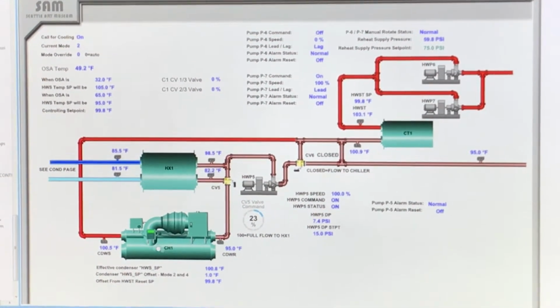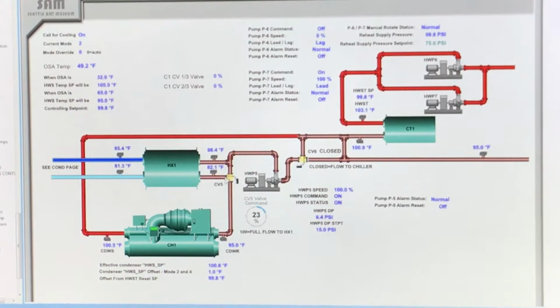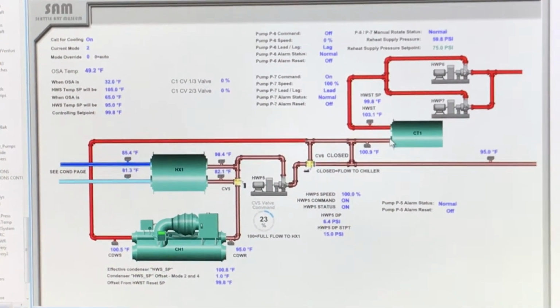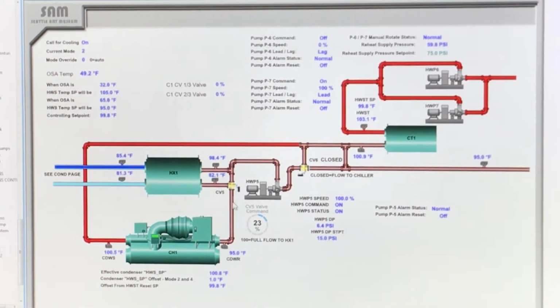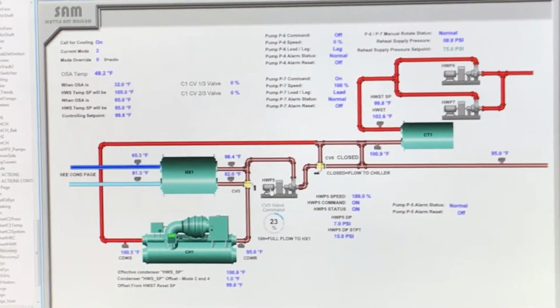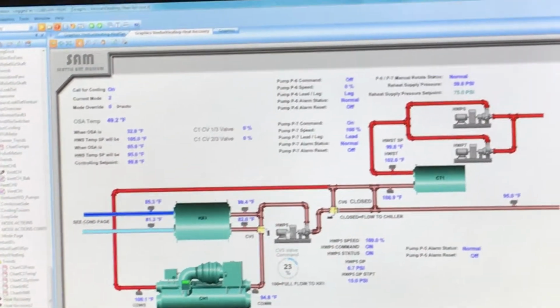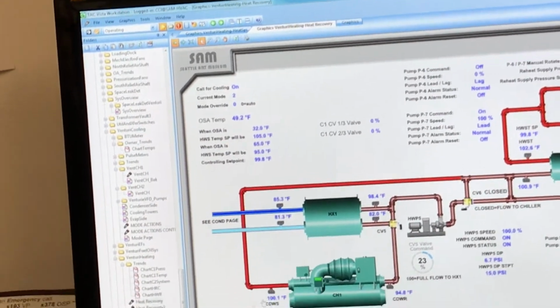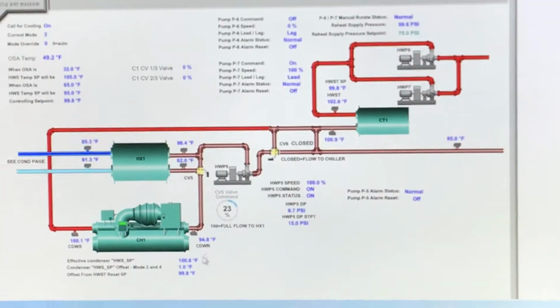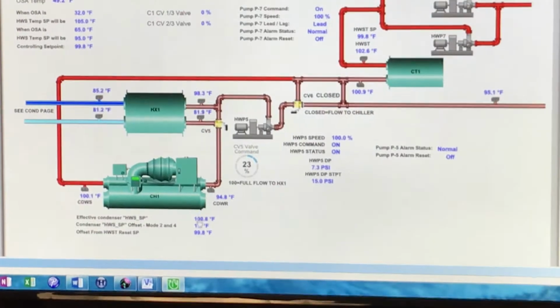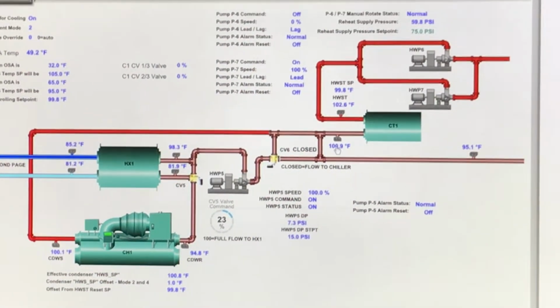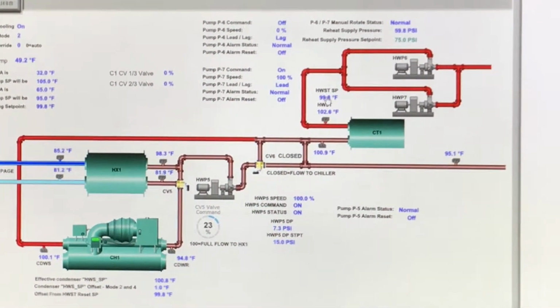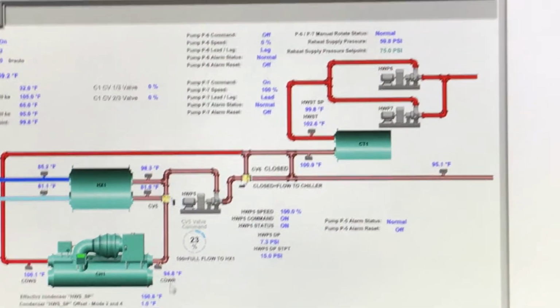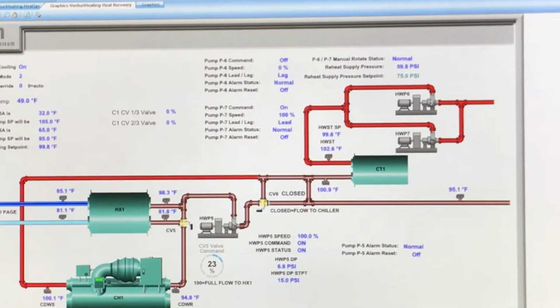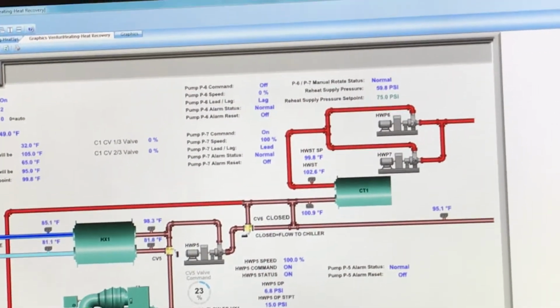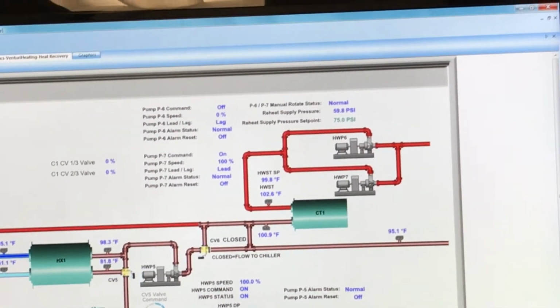Well, it's because this chiller is using the condenser water to heat it up. And that has to have a set point to control this valve. You don't want too much hot water coming in, and you don't want to overload your chiller coming back. So it modulates a set point down here, and what it does is it takes this set point right here, 99.8, and adds 1 degree to it to make it 100.8. Okay.